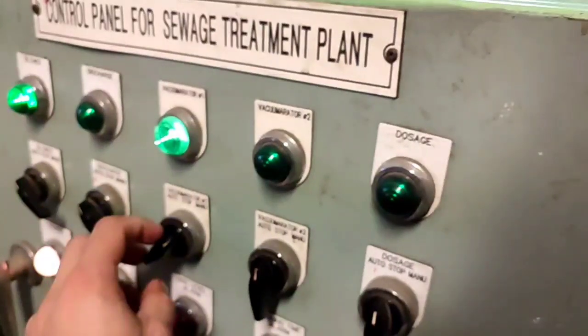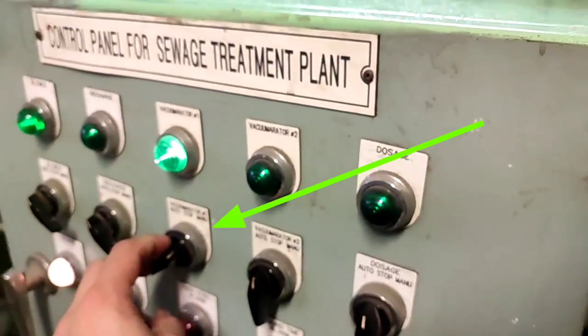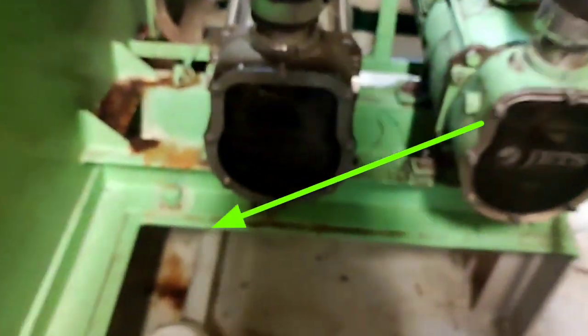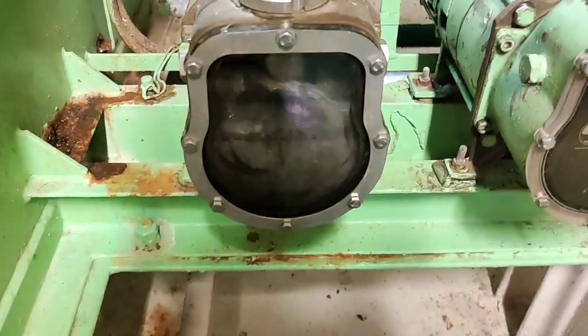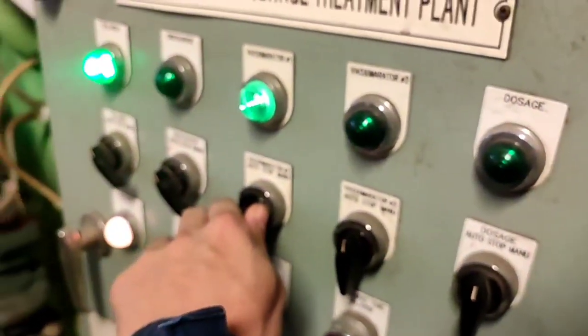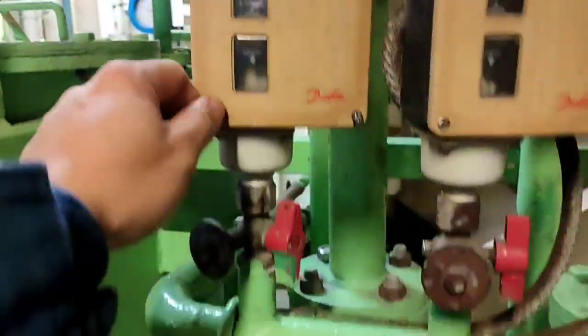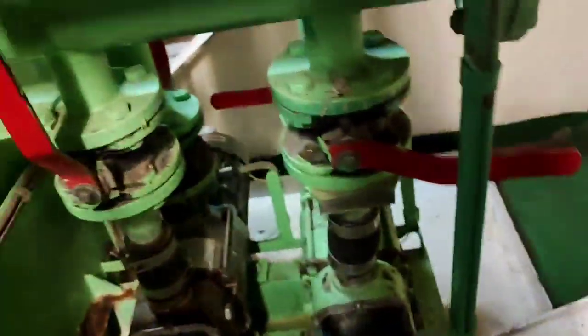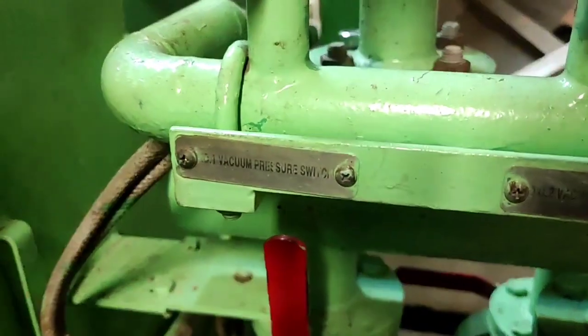First troubleshooting, you need to switch to manual mode so that you can check if the pump is running continuously. As you can see, the pump is running continuously and without problem in manual mode. It means there is a problem in auto mode.